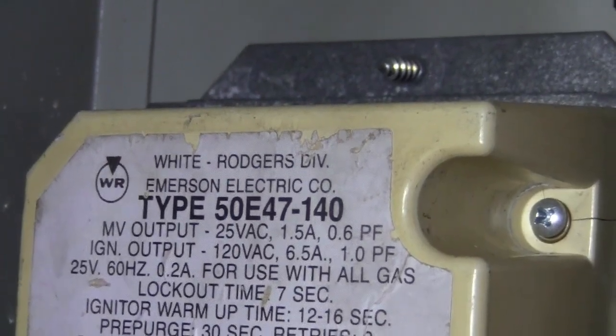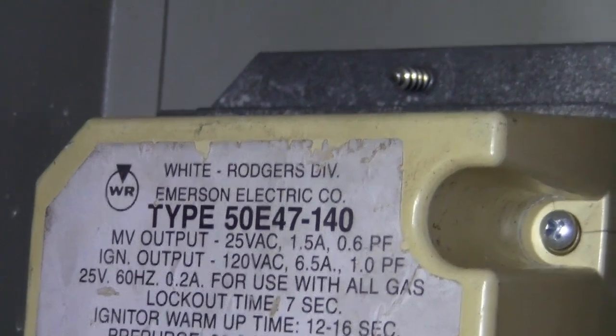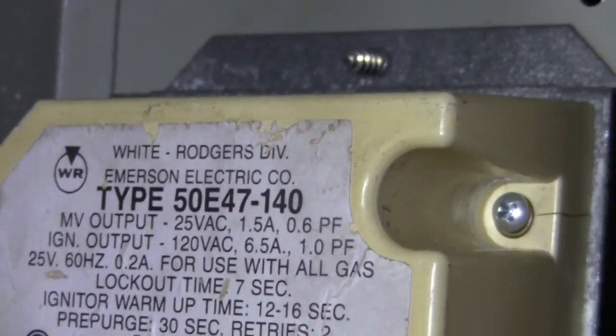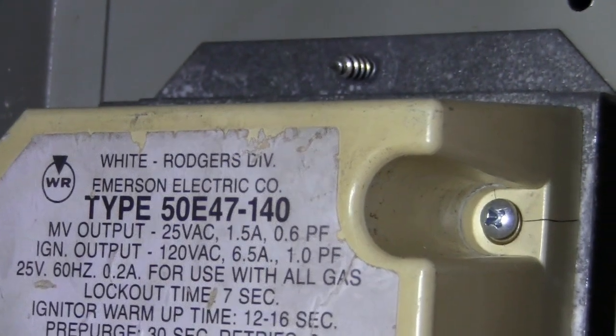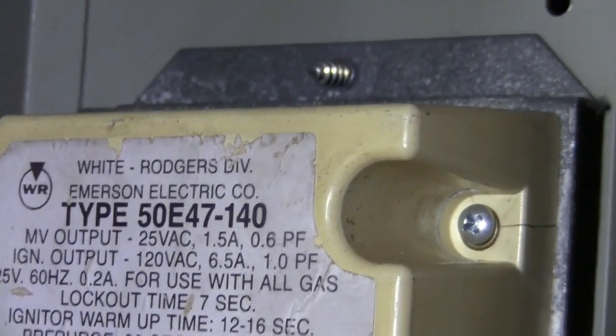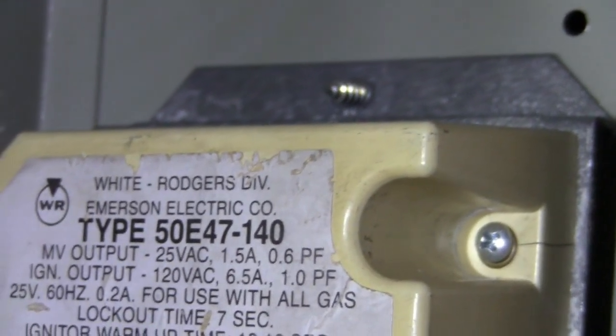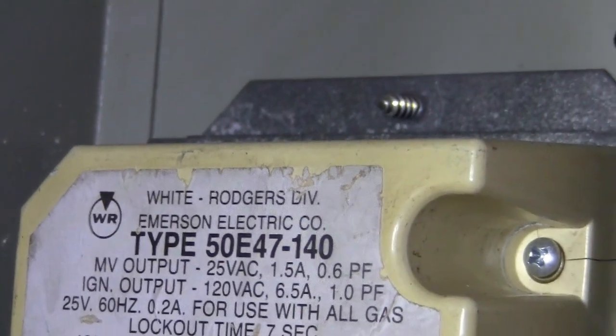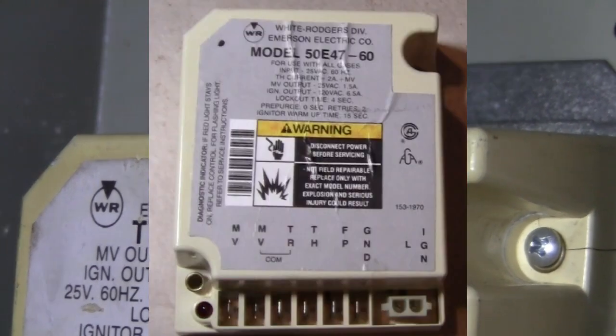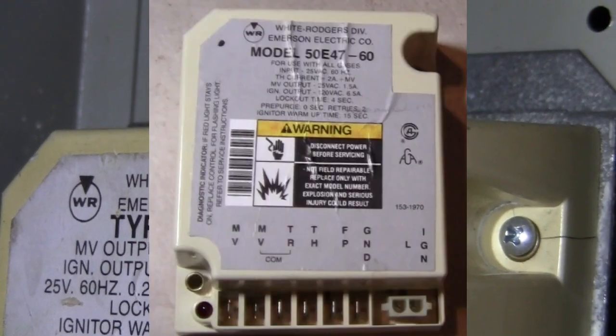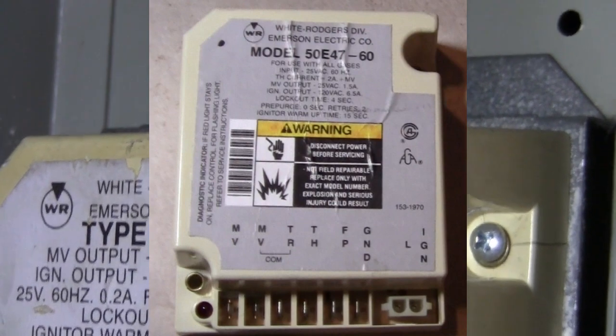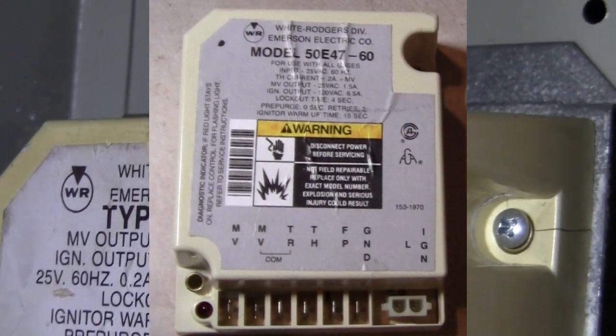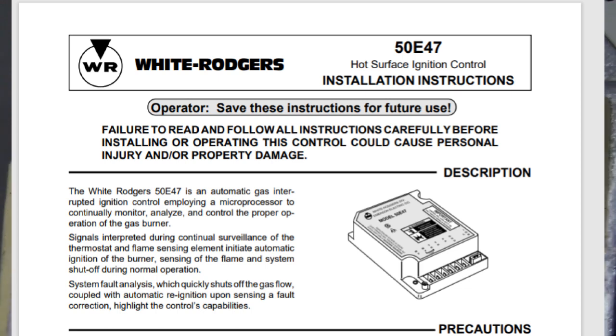Let's take a look at the model, the controller module. The model number is 50E47-140. Actually, this is not my original controller. My original controller is 50E47-60. It's slightly different from the 60 to the 140. The 140 has something called pre-purge.